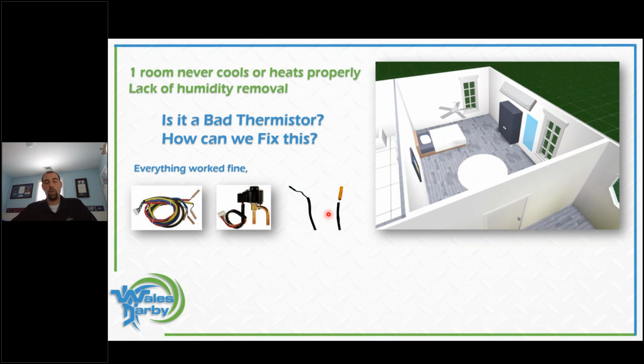So in that case, just changing a thermistor solved the problem, right? Just ohming them out is going to get you a long way and save a lot of time. So we just want to make sure, if that problem was right after the install, the install crew went in there, they installed everything, everything's great, have a nice day. Next day, you get a complaint. Last night, that one room upstairs, it didn't cool. There's still a lot of humidity. 3, 4, 5 guys go to a job. We get this a lot. That's why we're talking about it today.